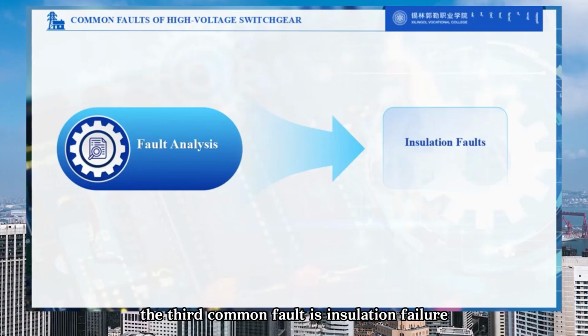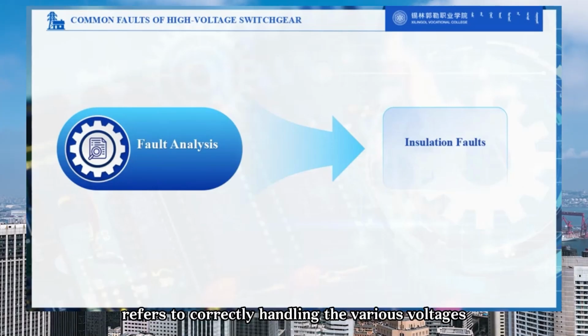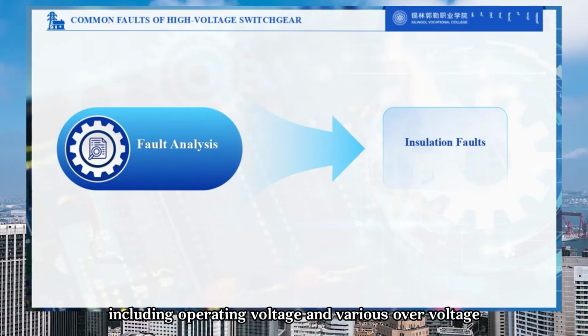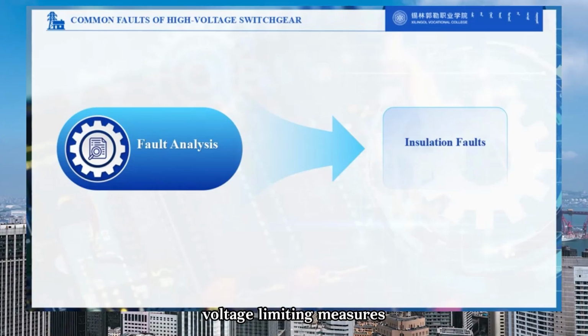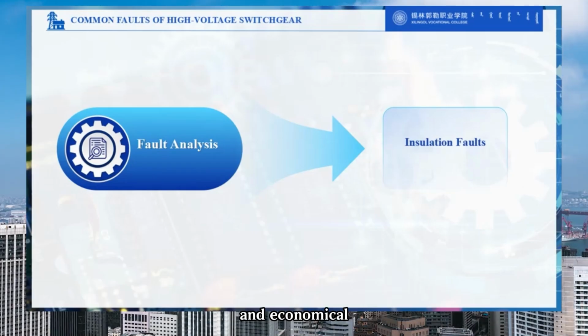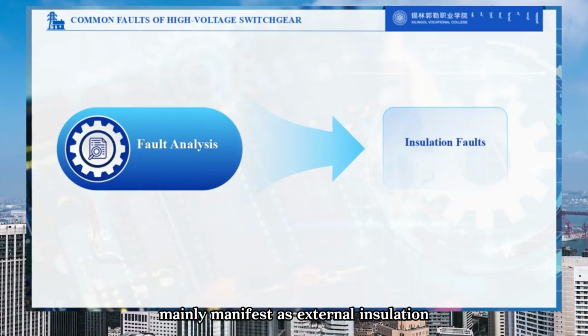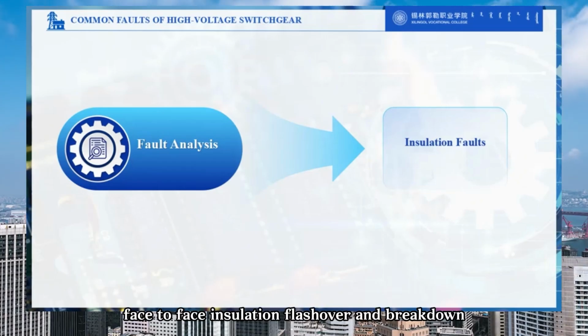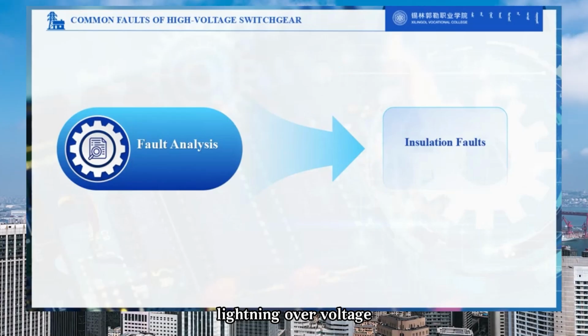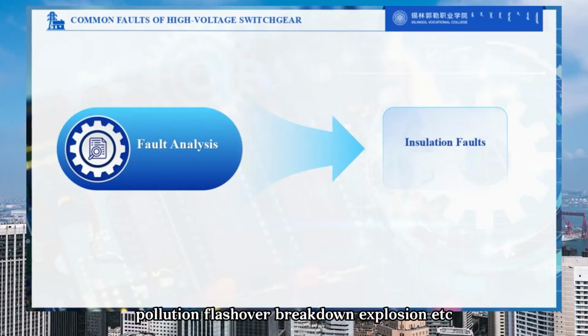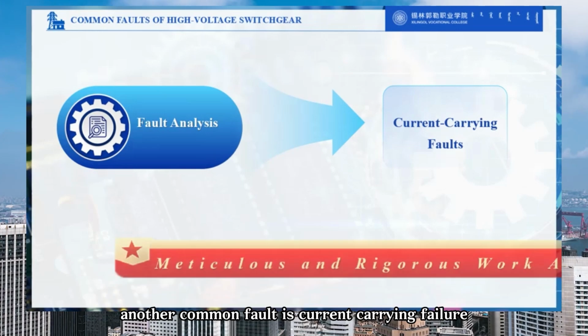The third common fault is insulation failure. Insulation level refers to correctly handling the various voltages applied to insulation equipment, including operating voltage and various overvoltages, and the relationship between various voltage limiting measures and insulation strength. The aim is to make the product both safe and economical, achieving optimal economic benefits. Faults related to insulation mainly manifest as external insulation flashover and breakdown to earth, internal insulation flashover and breakdown to earth, phase-to-phase insulation flashover and breakdown, lightning overvoltage flashover and breakdown of porcelain bushings, capacitive bushing flashover, pollution flashover, breakdown, explosion, etc.